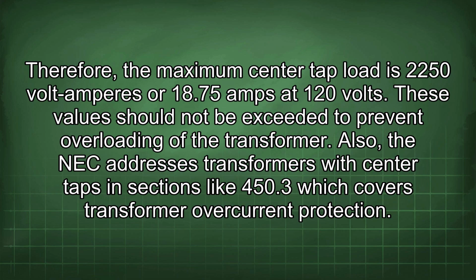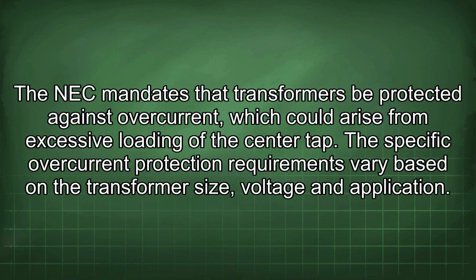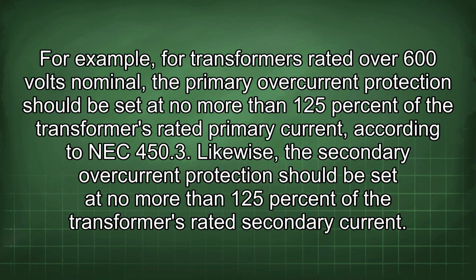Also, the NEC addresses transformers with center taps in sections like 450.3, which covers transformer overcurrent protection. The NEC mandates that transformers be protected against overcurrent, which could arise from excessive loading of the center tap. The specific overcurrent protection requirements vary based on the transformer size, voltage, and application. For example, for transformers rated over 600 volts nominal, the primary overcurrent protection should be set at no more than 125% of the transformer's rated primary current, according to NEC 450.3. Likewise, the secondary overcurrent protection should be set at no more than 125% of the transformer's rated secondary current.